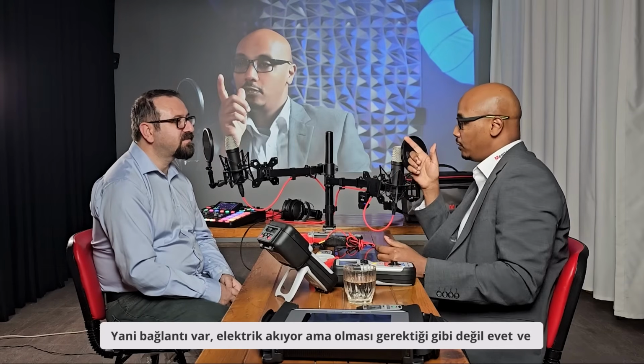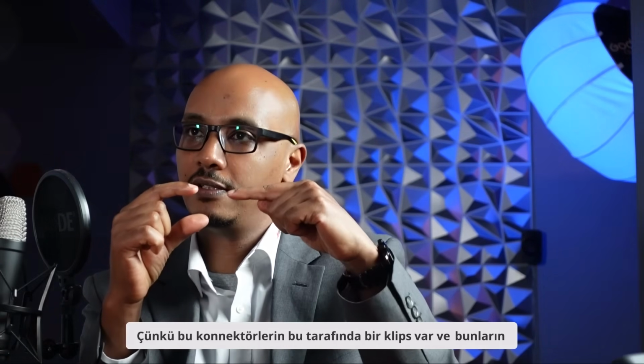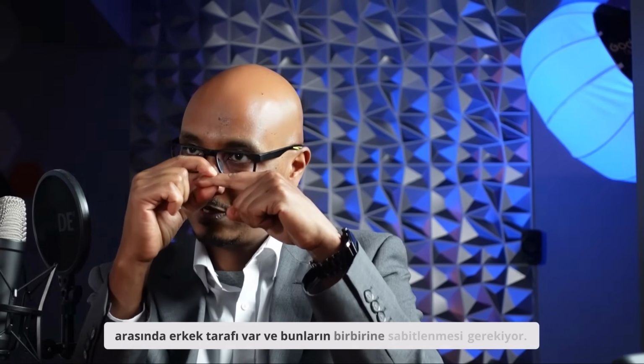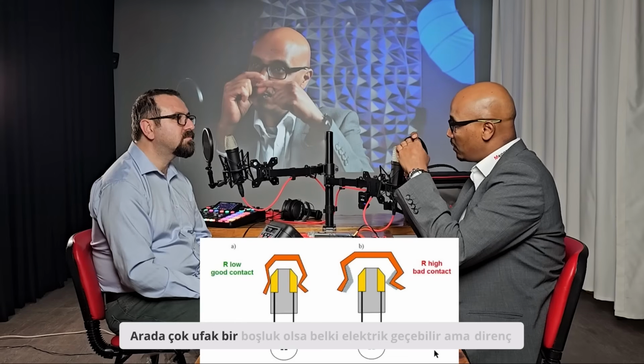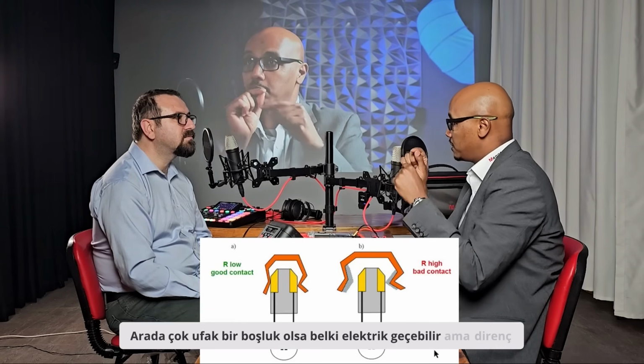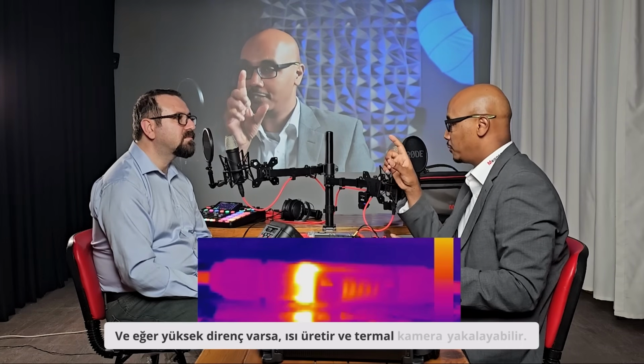If you do a thermal imaging survey on the bottom side, you will spot hotspots at that point, and that's how you know there's an issue. These connectors have a clip on one side and a male side in between that are supposed to fix together. If there's even a small gap, electricity may still flow, but the resistance is high, and high resistance produces heat that the thermal camera can spot.